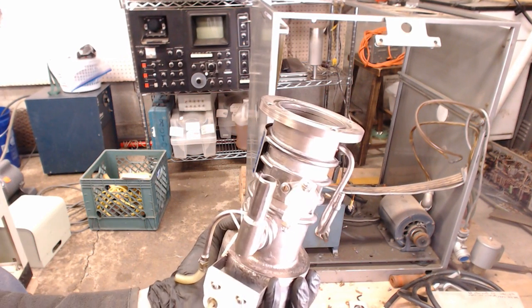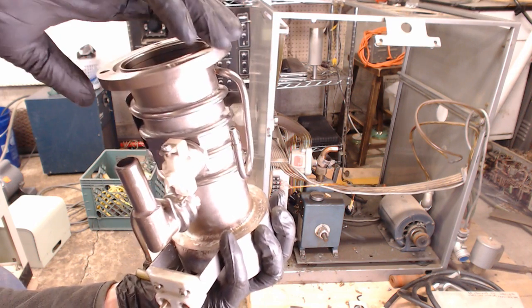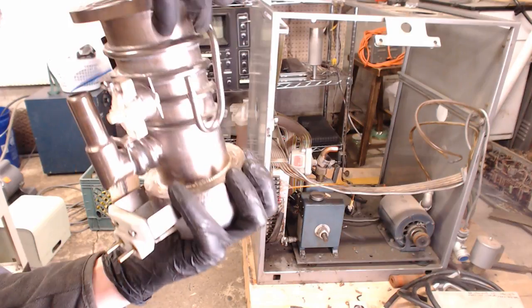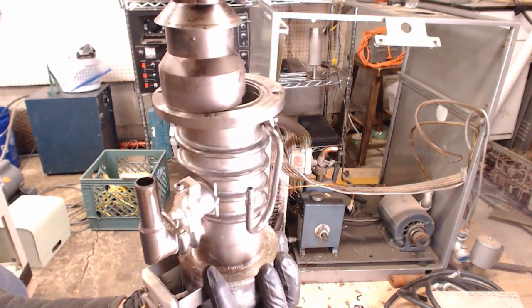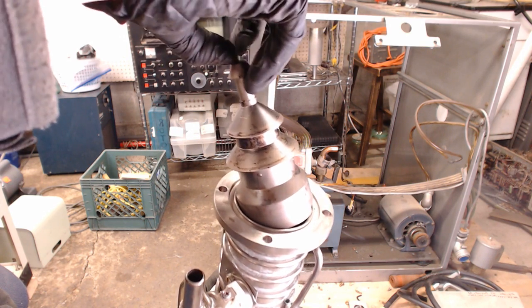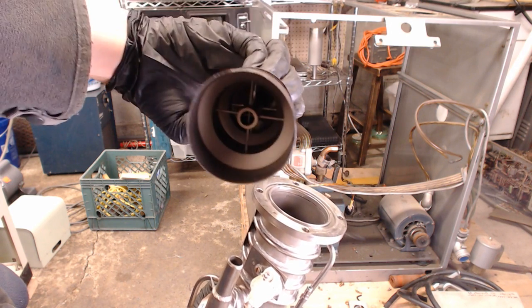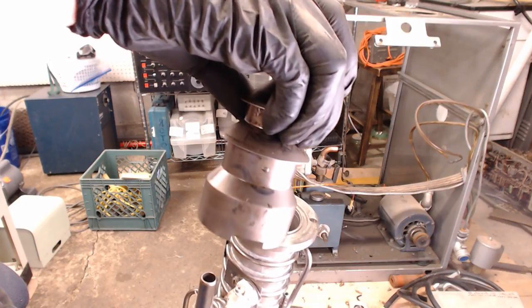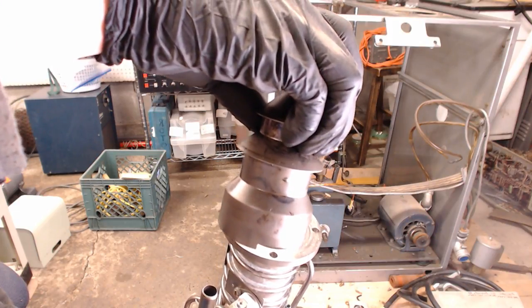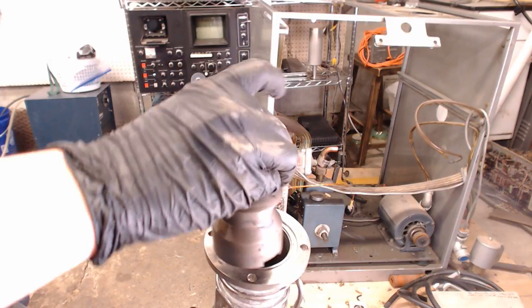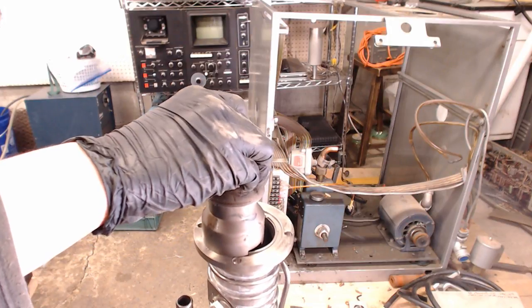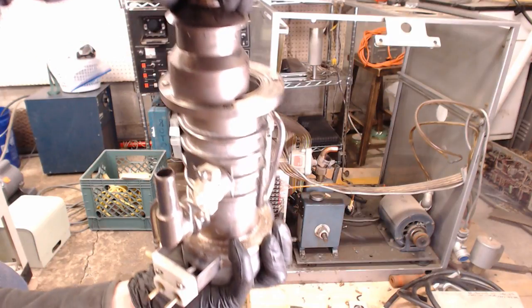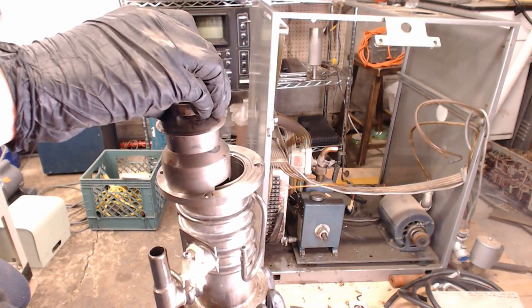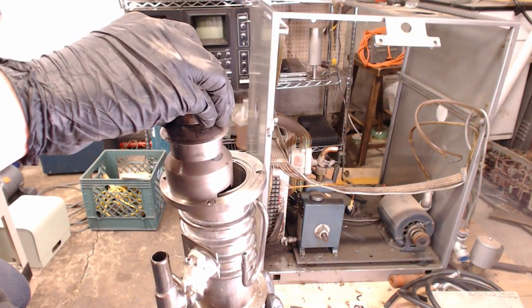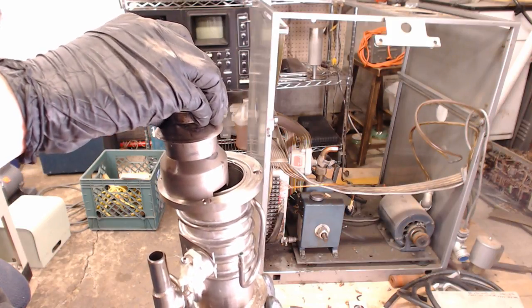So this is what most diffusion pumps kind of look like. Cylinder, water cooled, and at the bottom there's a heater cartridge. That heater boils oil and sends that boiling oil up what's called the Christmas tree, or they're actually known as the baffles, but they're called a Christmas tree. That boiling oil gets sent up inside of this thing, and then the vanes on these baffles direct the oil downwards, and the force of that vaporized oil, because it's boiled off, so it's vapor now, those oil vapors collide with air molecules. As they collide with air molecules, they knock the air molecules down. So you get a higher pressure of air coming out the bottom of the pump than you've got coming in the top of the pump. And so you can use this to get down to a higher vacuum by getting more air molecules out than a roughing pump or rotary pump can do.